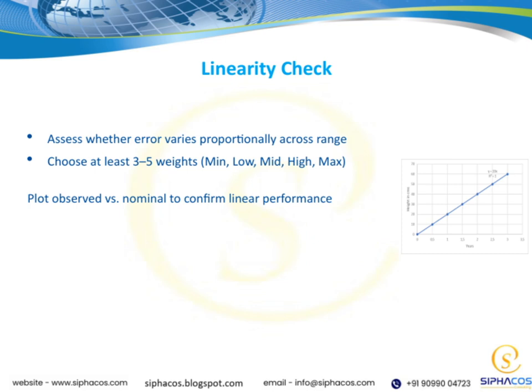Next, we plot the observed weights against the nominal weights. This helps us confirm whether the performance remains linear throughout the range. If the points form a straight line, that's a good indication that our system's error is consistent and proportional across all weights. This step is crucial because it ensures our measurements are reliable, especially when dealing with different weight levels. It ties back to the overall goal of validating the accuracy and consistency of our weighing system. So, always remember to check for linearity to maintain confidence in your measurements.